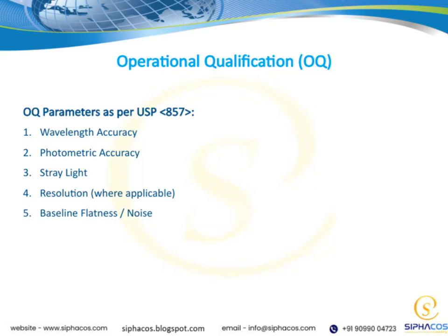Now, let's take a closer look at operational qualification, or OQ, which is a crucial part of validating our analytical instruments. According to USP 857, there are several key parameters we need to verify during OQ to ensure the instrument is performing reliably. First, we have wavelength accuracy. This means we need to confirm that the instrument measures wavelengths correctly, because precise wavelength measurement is essential for accurate analysis. Next is photometric accuracy, which involves verifying that the instrument's absorbance readings are accurate and consistent, ensuring reliable quantification.